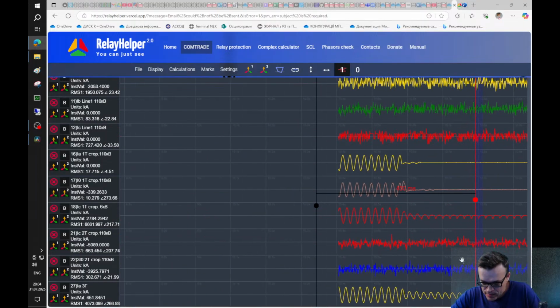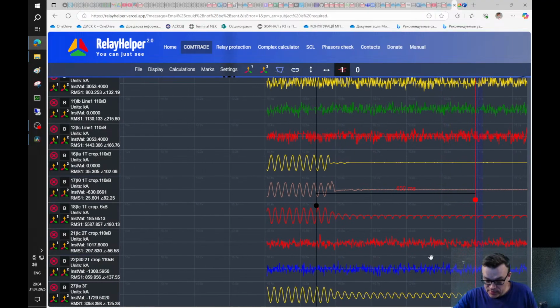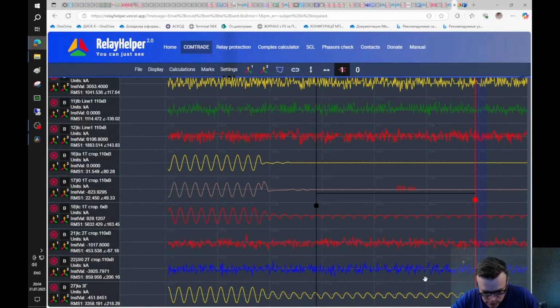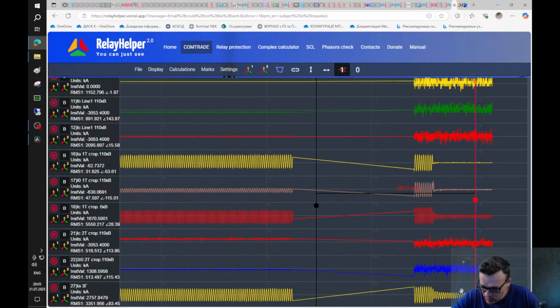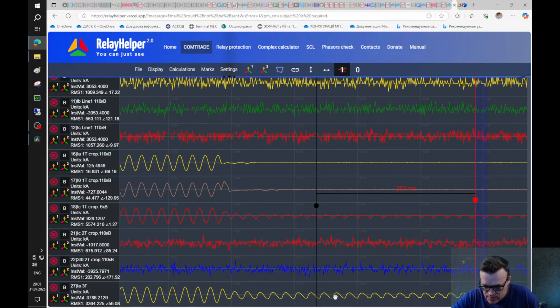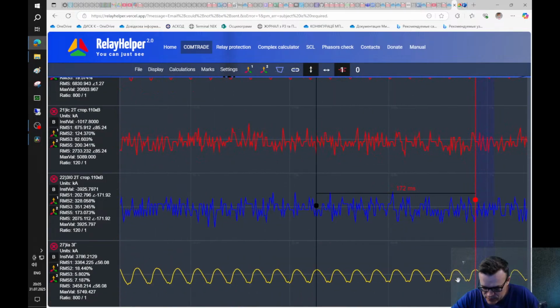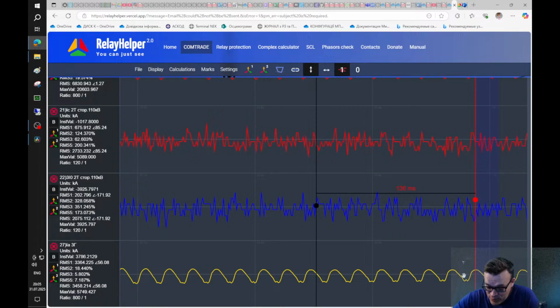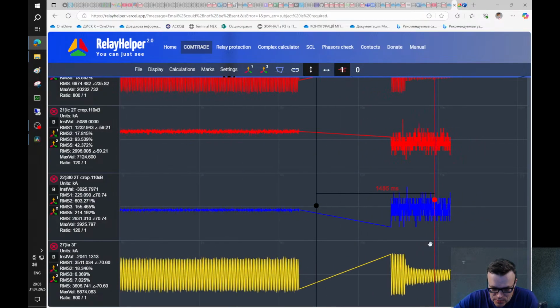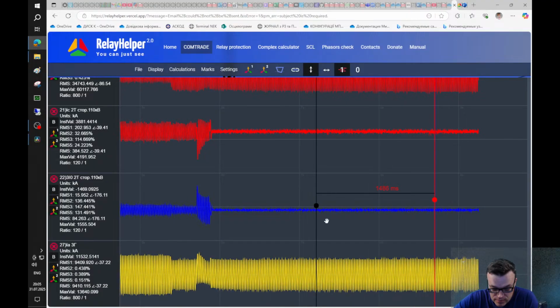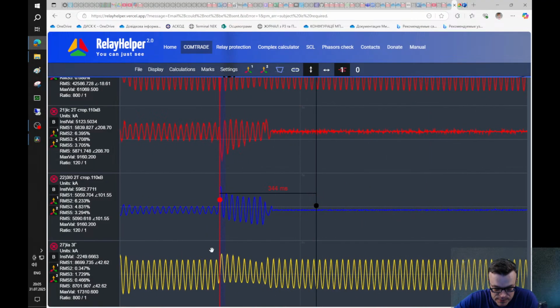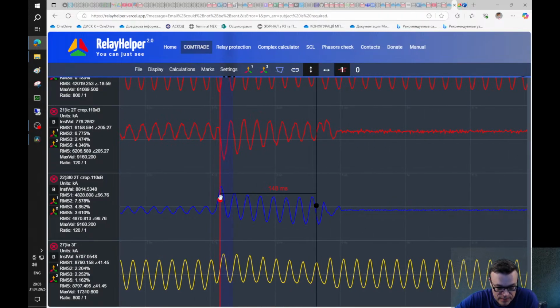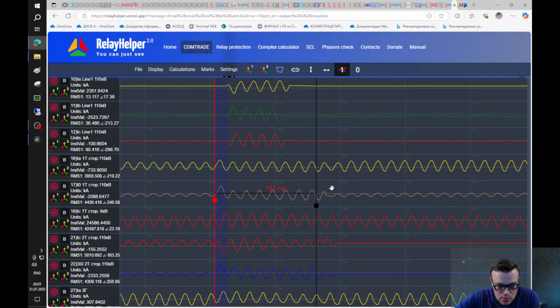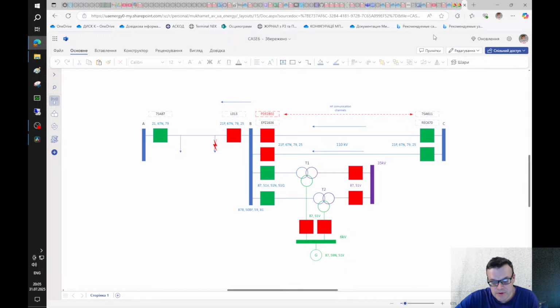So the generator returned to normal. Like, it's very difficult to say normal because it was stressed a lot, and you can see by the waveform of the current that it was a hard time for it. So I would want to say that nothing happened to the generator. The most stressful place, I believe, was here with non-synchronous automatic reclosing. So I believe that I said mostly everything.